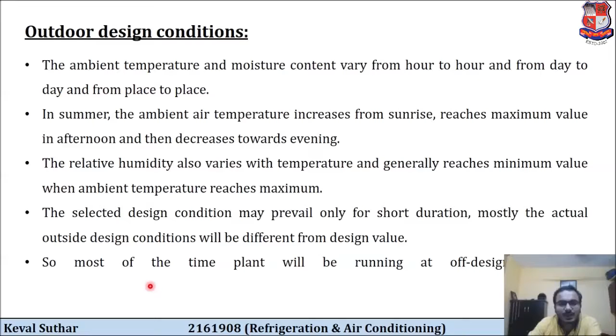The selected design condition may prevail only for a short duration and mostly the actual outside conditions will be different from the design value. So most of the time the plant will be running at off design conditions. Let us say we have designed a cooling system for 35 degrees Celsius outdoor condition and 60% moisture, but this design point will not be there for all 24 hours. It will keep on varying. That's why most of the time the plant will be running at the off design condition.